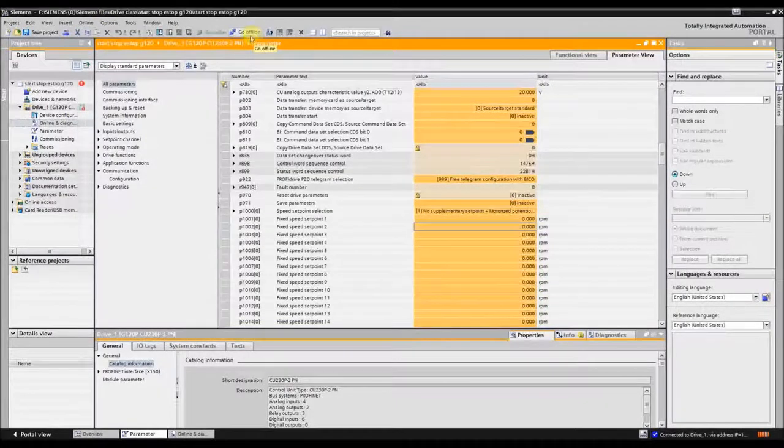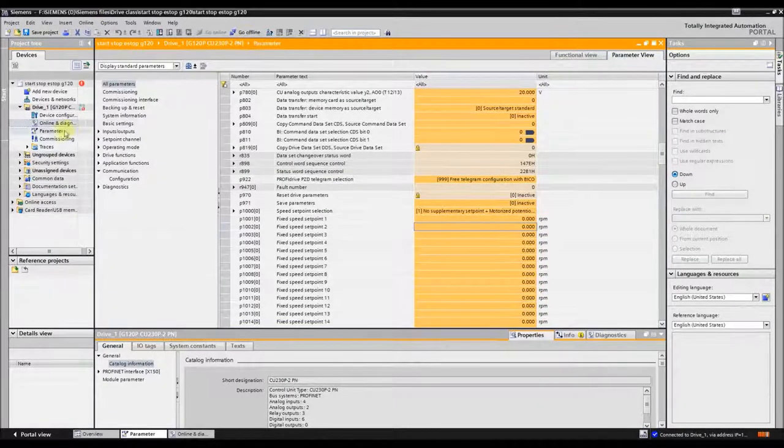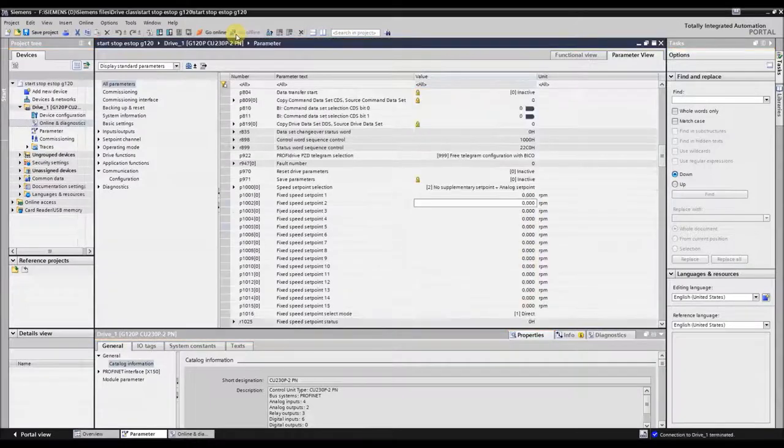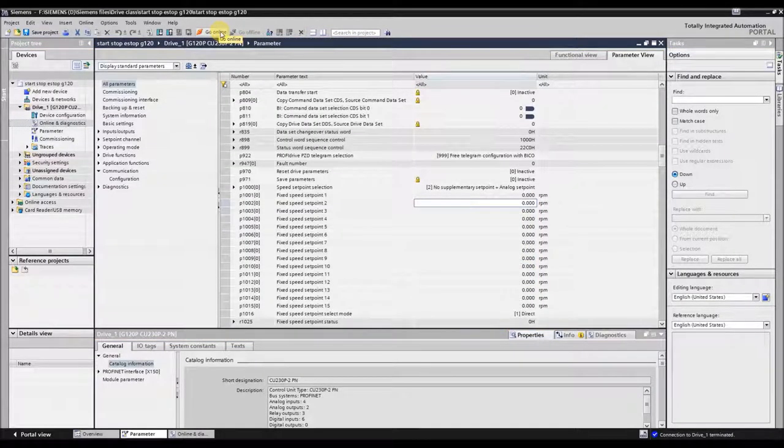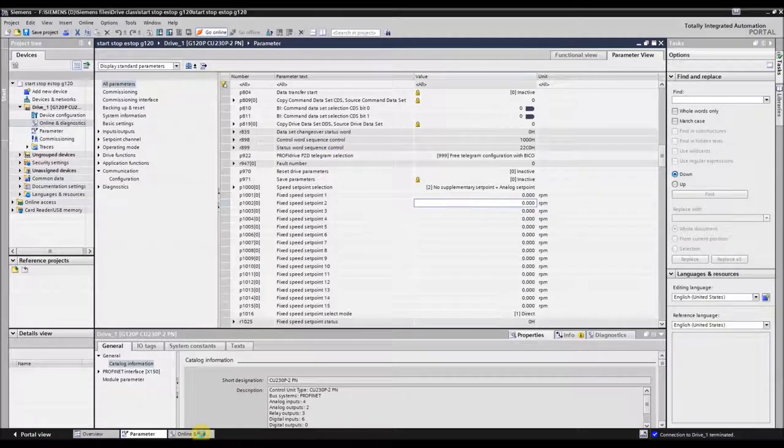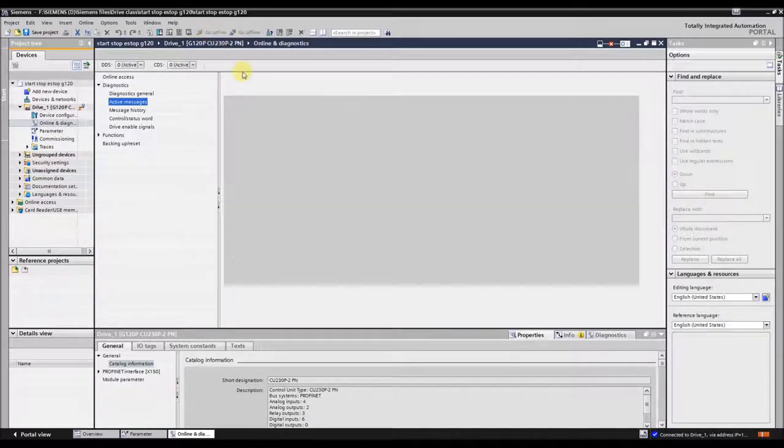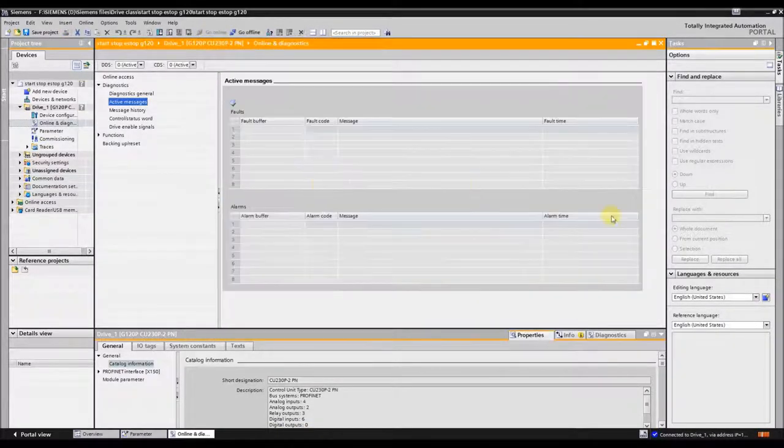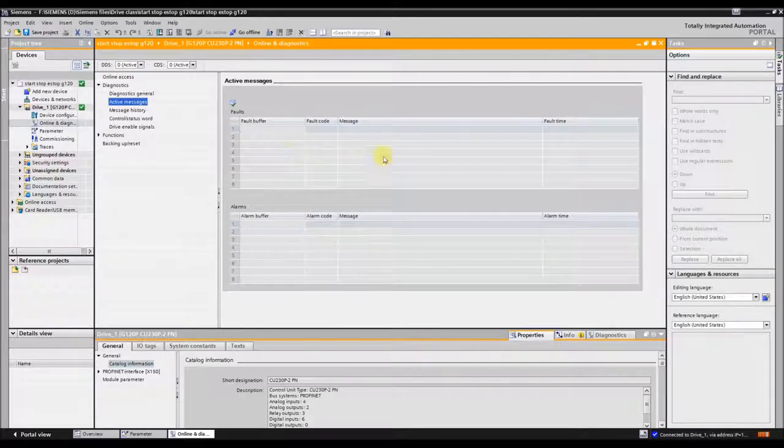I'm going to go offline with the PLC and restart the G120. Now I click go online and look at my alarm buffer. The cyclic communication error is gone. Thank you for watching.